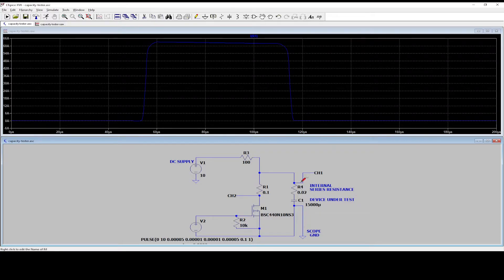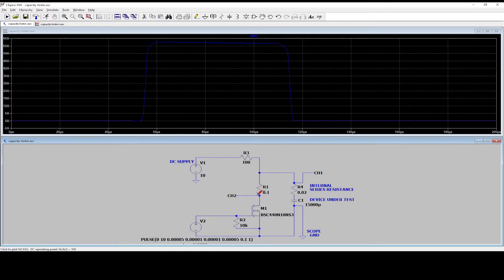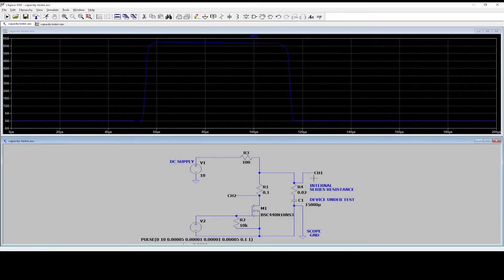So now we have 62 amps. And then we have the voltage drop. And then you can calculate the internal resistance and you will get very close to the 20 milliohm of internal resistance.